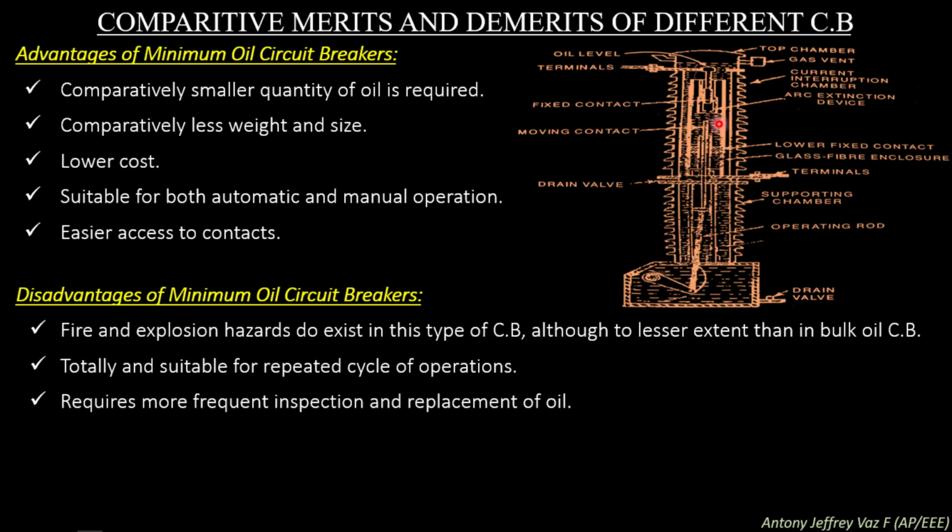Since only a small quantity of oil is present in the minimum oil circuit breaker, due to the presence of arc, high carbonization occurs and decomposition of the oil is also high. So we need to frequently replace the oil present in the minimum oil circuit breaker.